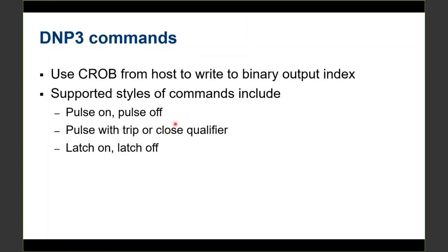These trip and close operations are the most common because they provide a way to send the same command on the same index. So I can send a pulse on command with a trip qualifier to open the breaker on index 0, for example, and send a pulse on command with a close qualifier on index 0 to close the breaker.